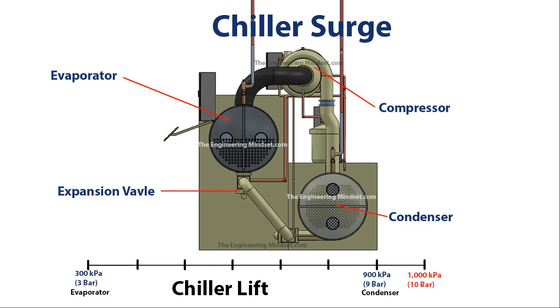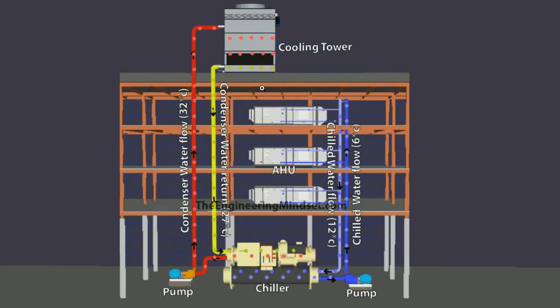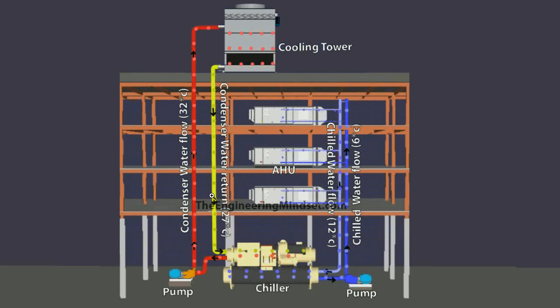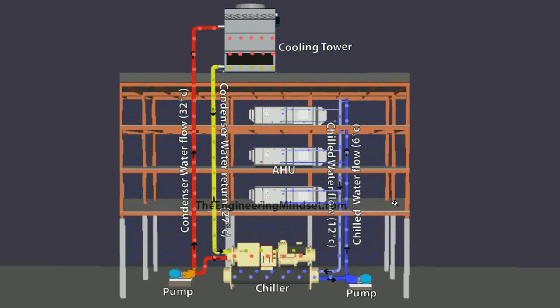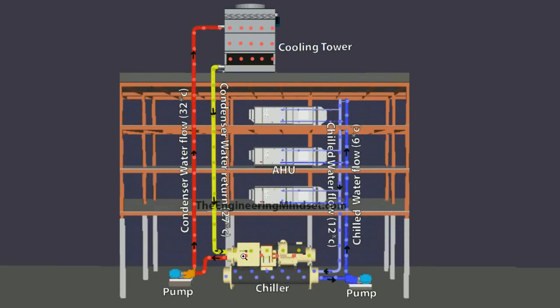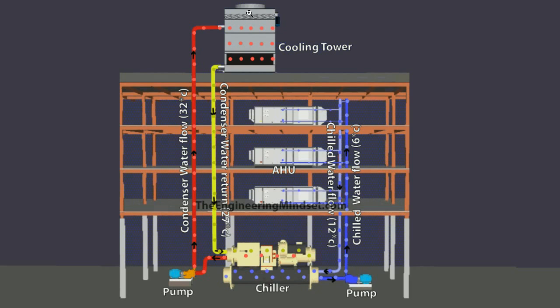So what causes chiller surge? We know it's going to be an increase in pressure in the condenser. The majority of the time it's usually something to do with a cooling tower or the flow of condenser water. If a partial blockage occurs in the condenser return line, the flow rate will drop below the minimum required, and the condenser won't be able to dump its heat, raising the pressure. If the cooling tower is unable to reject enough heat, the water temperature increases, restricting how much heat the condenser can absorb. This might be caused by a drive belt breaking or the motor having a fault.